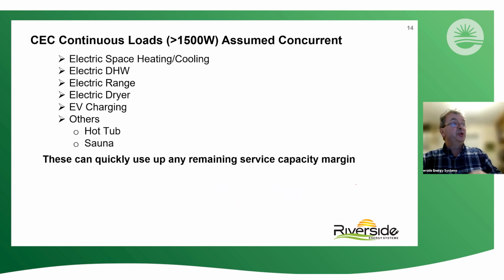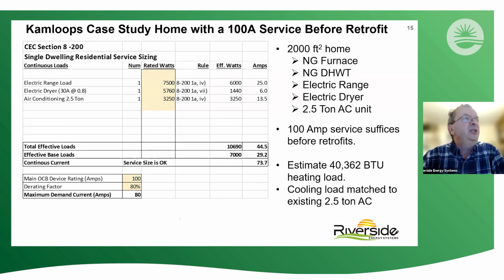So the next thing is continuous load. So we take things like electric space heating and cooling, domestic electric hot water tanks, electric ranges, dryers, EV charging, hot tubs, etc. And some of these devices, like an electric range, can be derated to some extent. But fundamentally, we're more or less assuming that these are all running concurrently. So it adds up very quickly. And if we take the case study Kamloops house, which just happens to be my house, which has natural gas furnace, natural gas hot water, an electric range, an electric dryer, and a 2.5 ton air conditioner. It turns out when I apply these rules that I'm just under what I'm allowed. So my service is currently compliant.